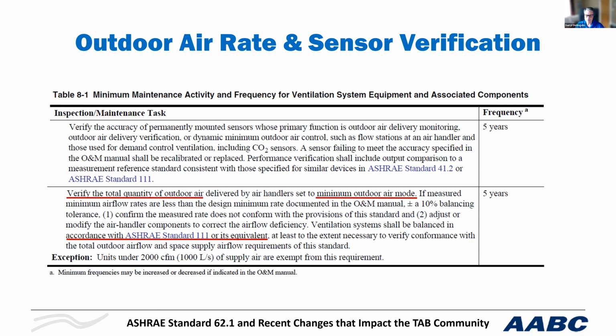And of course, we found out during COVID, there's a lot of deferred maintenance. That was one of the challenges: systems weren't performing as they should because they weren't treating this document as an evergreen document and keeping it up. So what I'm saying to all you listening today, this should be recurring revenue for TAB and commissioning companies. The standard is saying you must do this, you shall do this. And you should be going out selling your services and saying, hey, we've got to verify it to make sure things are going well. So when the next pandemic comes around, the systems are ready.